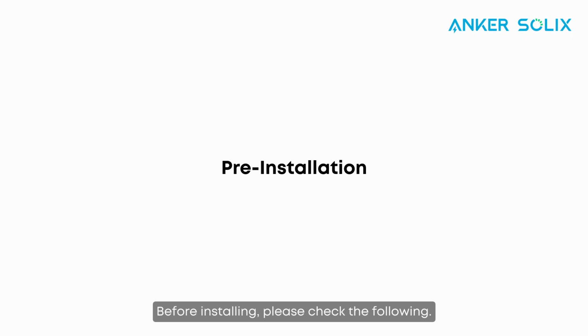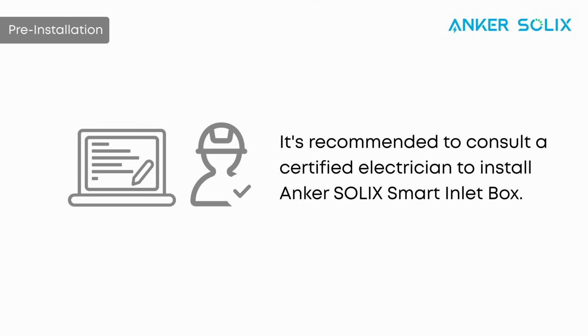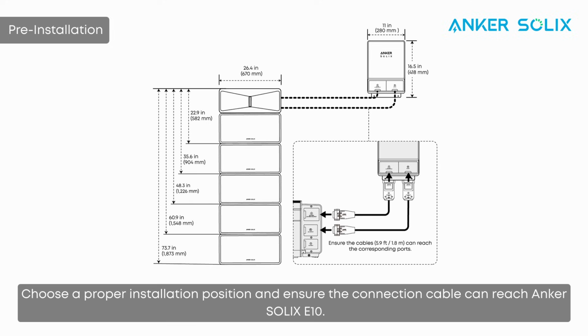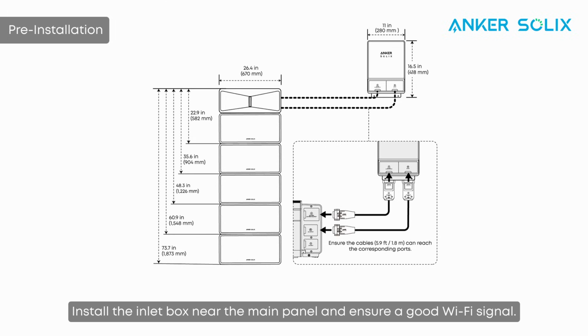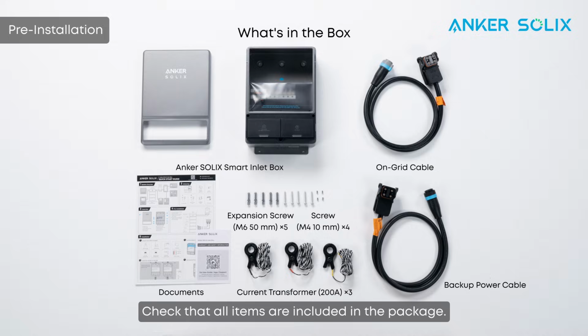Before installing, please check the following. It's recommended to consult a certified electrician to install Anker SOLIX Smart Inlet Box. Choose a proper installation position and ensure the connection cable can reach Anker SOLIX E10. Install the inlet box near the main panel and ensure a good Wi-Fi signal. Check that all items are included in the package.